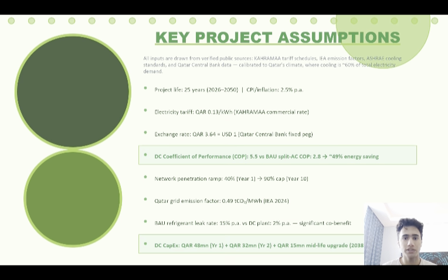District cooling is a more efficient cooling system than traditional air conditioning because one central plant can cool many buildings while using much less electricity. For example, in a project, the district cooling system has a coefficient of performance (COP) of 5.5 compared to 2.8 for conventional air conditioning systems. This means it can provide the same cooling while using around 49% less energy.